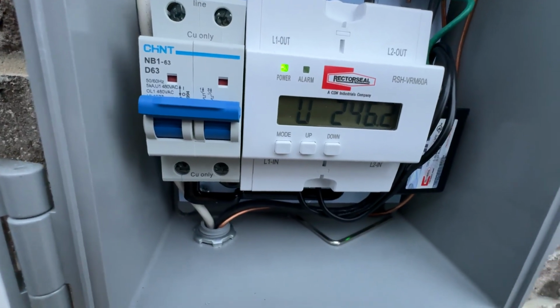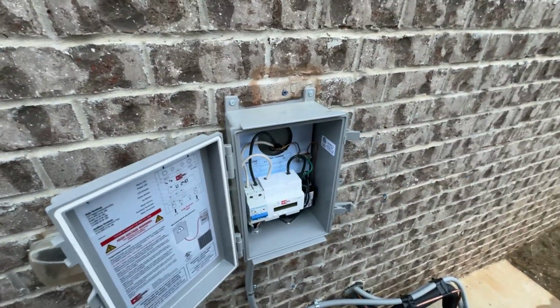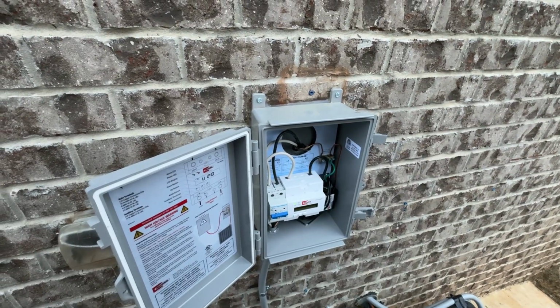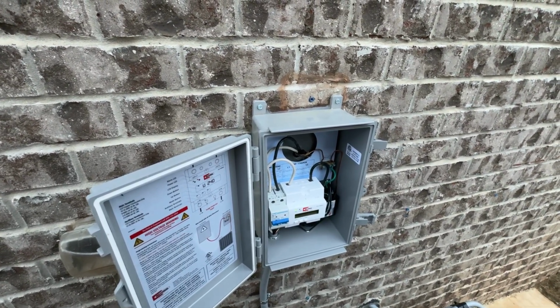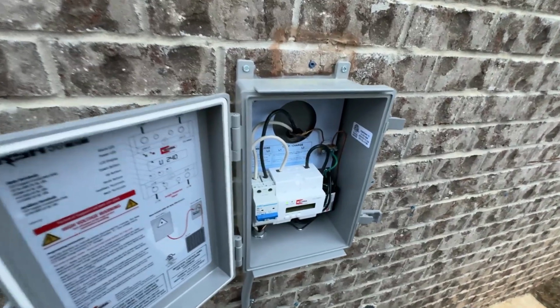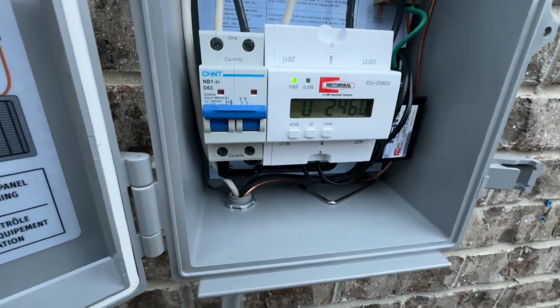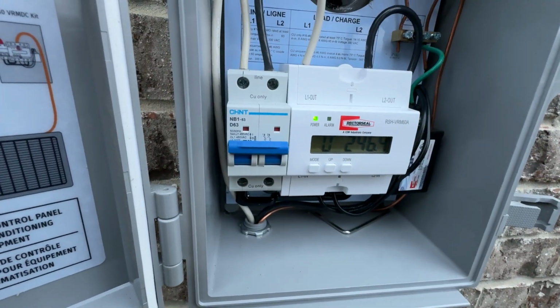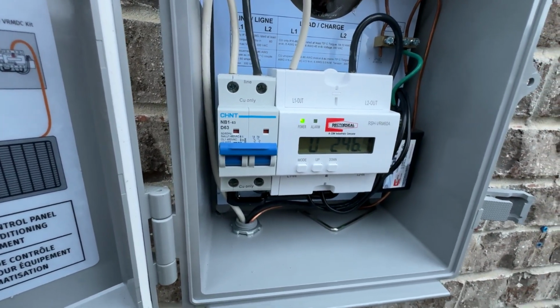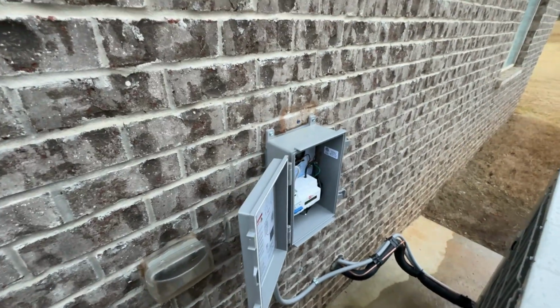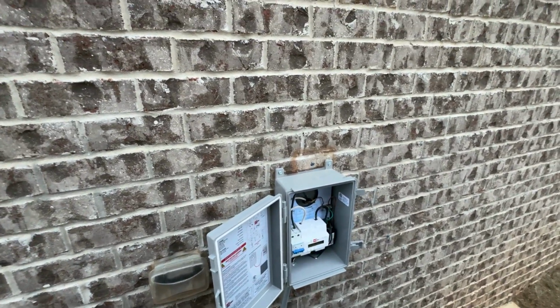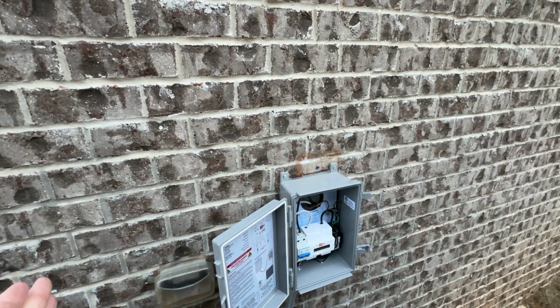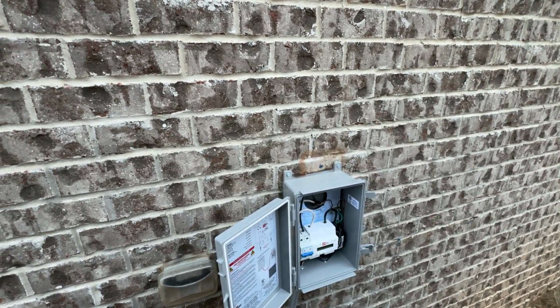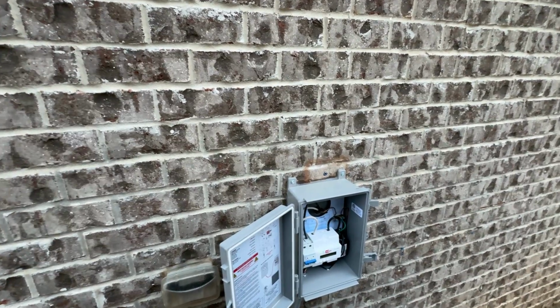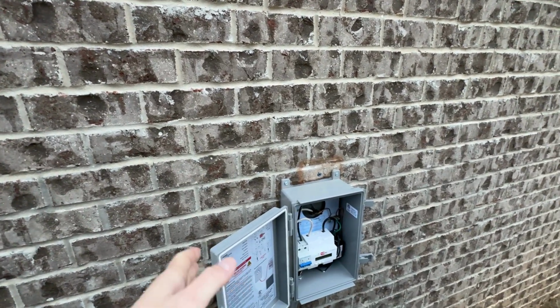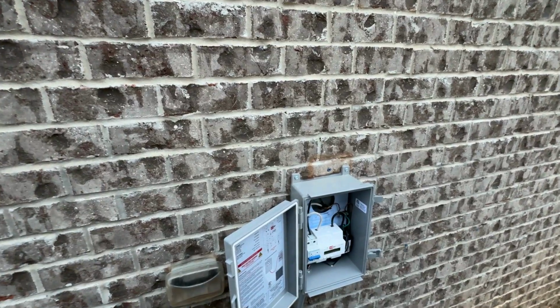246.2 currently. And that will fluctuate, but the thing you have to understand, a normal house is 120/240, right? Double 120 is 240. On install day, I was running about 252, 253. We saw 254 a couple times, and that's unacceptable. Above 252 is not permissible. The utilities are allowed a 5% overage from 120/240 and a 5% under. So basically you're looking at 114 on the low to 126 on the high. That would give you your 228 to your 252.